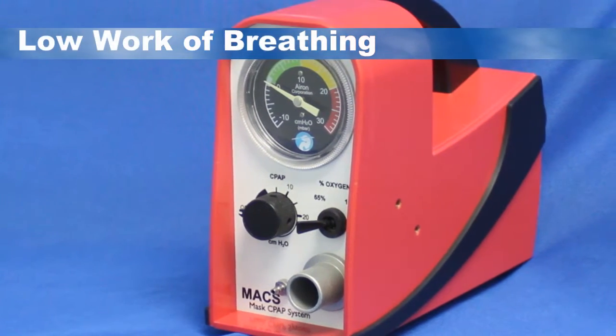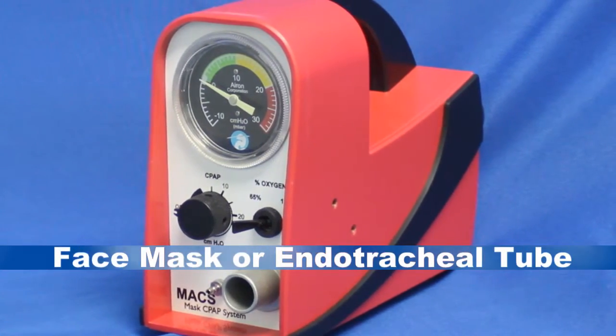MACS' key feature is its ability to provide true CPAP with low work of breathing, automatic sensitivity, and up to 140 liters per minute flow rate for the spontaneously breathing patient. With this excellent CPAP system, you can support patients via face mask or endotracheal tube.